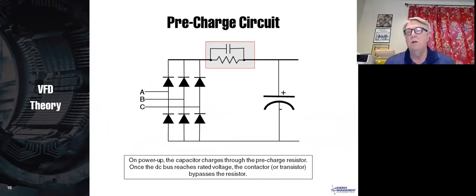Now we have a pre-charge circuit in there. I won't mention too much about this, except to say that when you first energize the drive, you can have very, very high currents into the capacitor because it looks like a short circuit. So all drives have pre-charge circuits, and this is a simple pre-charge circuit composed of a resistor and a contactor. So the capacitor charges through the resistor that limits the current into the capacitor. It keeps you from tripping breakers and fuses, but most importantly, it keeps you from blowing up the capacitor.